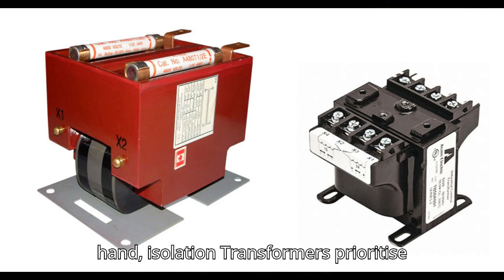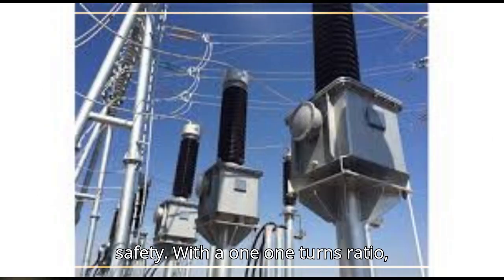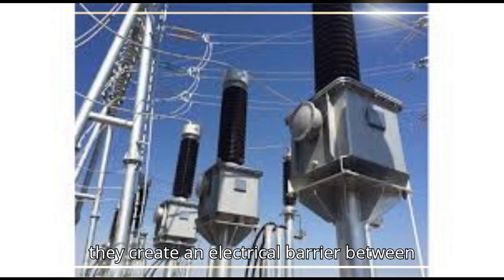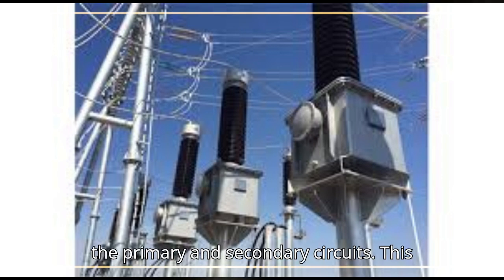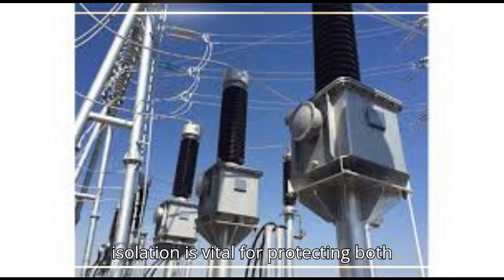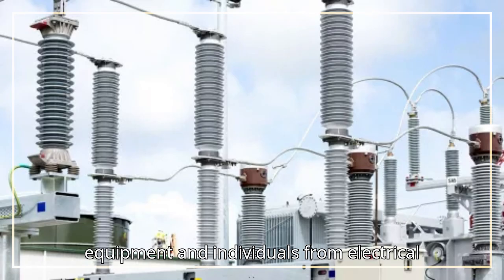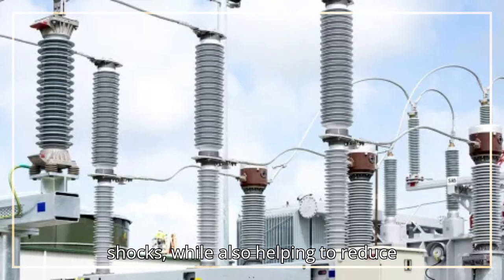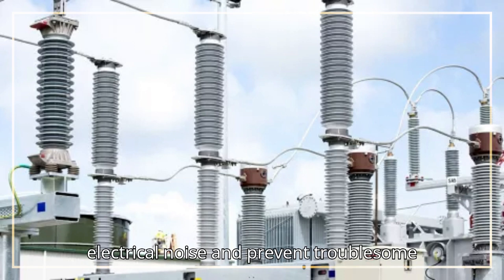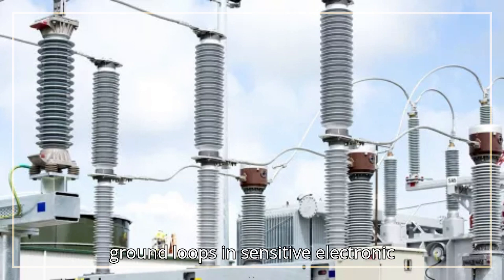On the other hand, isolation transformers prioritize safety. With a 1:1 turns ratio, they create an electrical barrier between the primary and secondary circuits. This isolation is vital for protecting both equipment and individuals from electrical shocks, while also helping to reduce electrical noise and prevent troublesome ground loops in sensitive electronic systems.